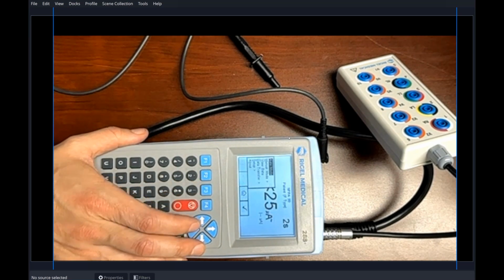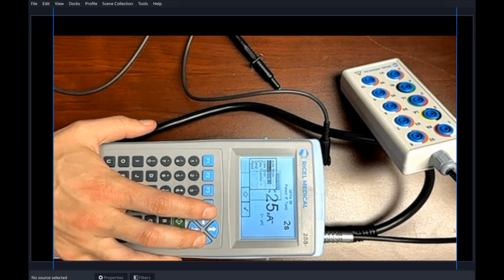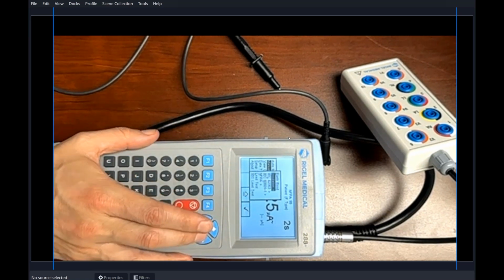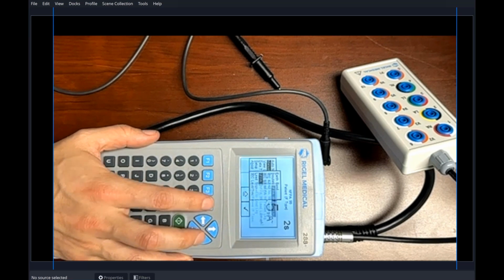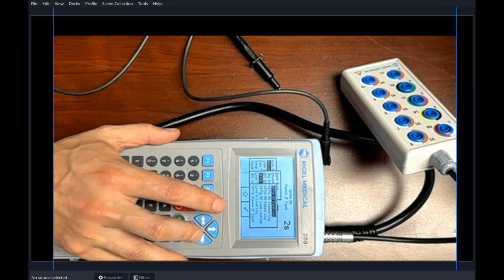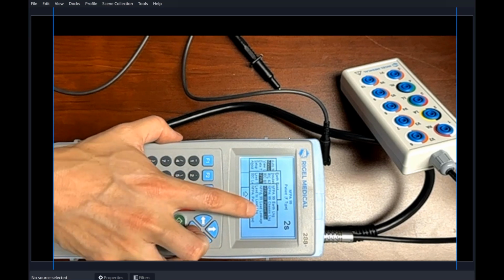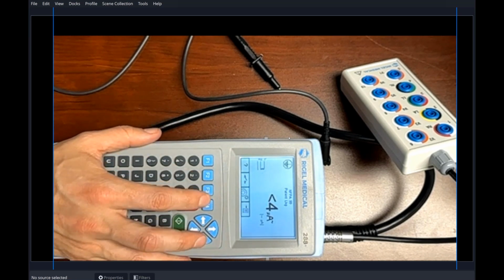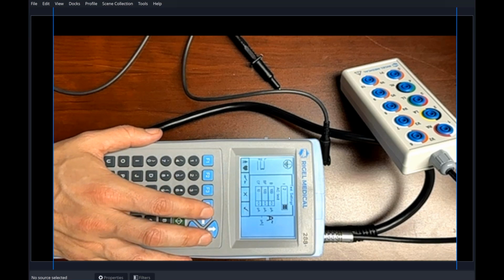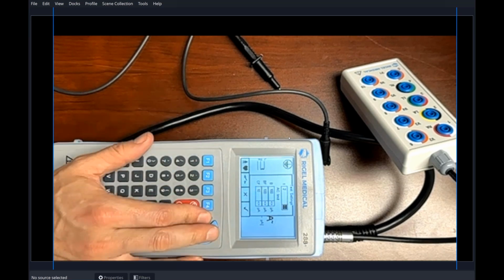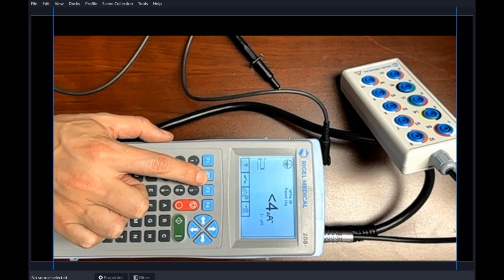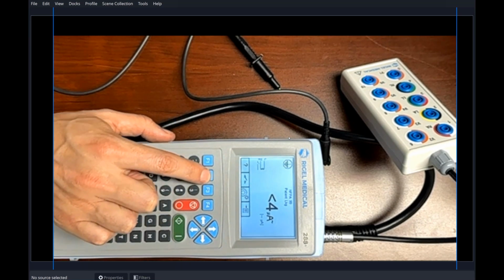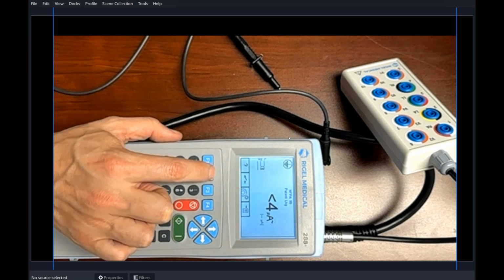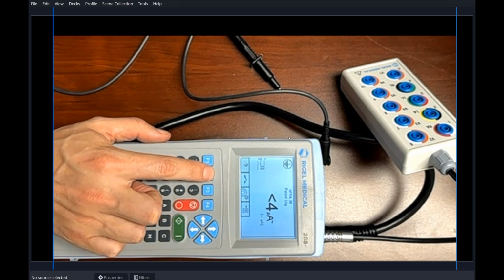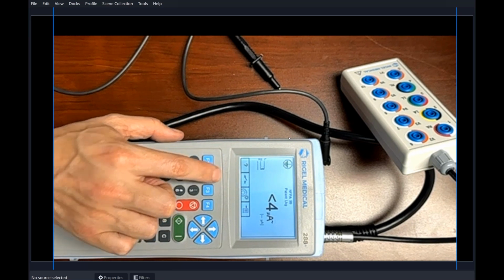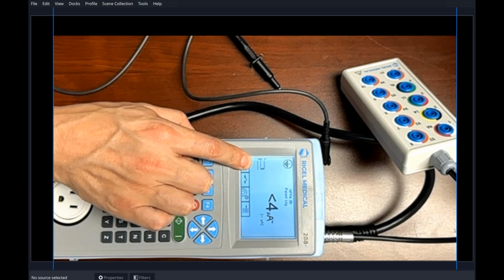The 288 also has a manual mode built in. And here's where you can just select each individual test separately: insulation, NFPA 99, so earth leakage, chassis leakage, patient leakages. You can go in there and just perform any manual tests within the 288. You can change the settings and the limits, unlimited, and then this function key here, F2, will change any of the fault conditions. So that's now earth open, reverse polarity, open earth, and then back to a standard condition for the device under test.